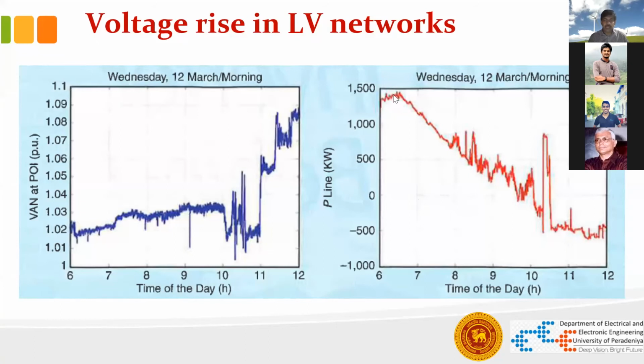In the early morning, you can see the feeder is bringing power from the grid somewhere around 1,500 kilowatts. As the solar picks up, somewhere around 10 a.m., the power flow in the feeder becomes zero, and you can see the voltage is slowly rising. Then as there is more excess solar generation, the power becomes reversed, we call it reverse power flow, and the voltage has gone really up.